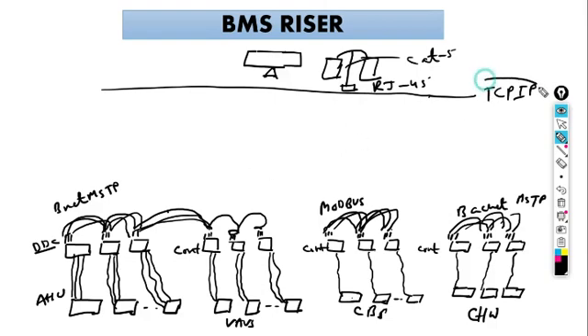This is one kind of communication protocol, and BACnet or Modbus or Profibus or CBus are other kinds of communication protocols. If we just stretch a wire from here to here, it will not communicate. So we must have a translator in between. In that scenario, we have a router to translate these protocols to the TCP over IP protocol.